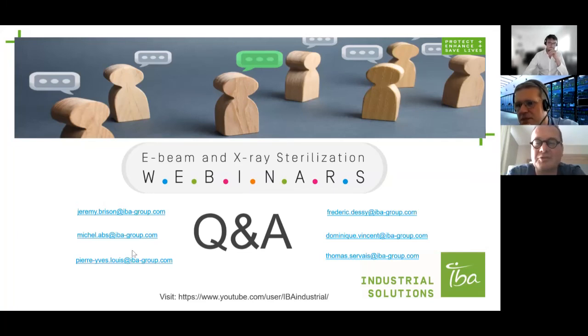Thank you for this question. Effectively, that's one of the challenges we have. Putting in an online dosimetry system will be quite difficult, because any electronics will mainly be destroyed by the beam. So what we mainly record are other parameters, like the beam current and the speed of the conveyor, and we store all that information in Beagle. This means that using this information we can go back to the dose that has been delivered to the product. So that's mainly how we are dealing with that aspect.